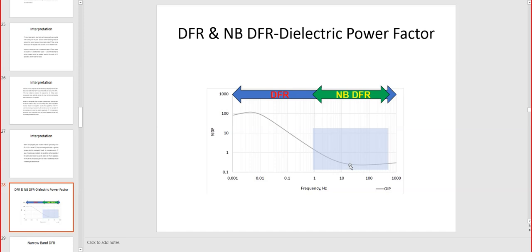A single point that we had before the reading is going to be on the graphic, but as you can see, it is normal that in the enlarged frequency response at the very low frequency we're going to have a higher dielectric power factor. So you see the losses increase at low frequency, and then they decrease after 1 hertz, coming back down. In that area, 10 hertz and above 10 hertz, we are in the range that we are used to seeing for the power factor.